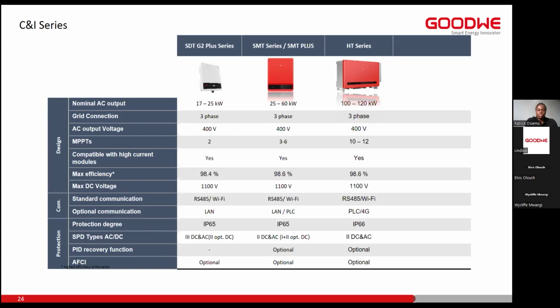And we do have high efficiencies. You see our maximum efficiency is 98.4%. And we support big string connections. You see our MPPT is able to handle up to 1100 volts DC. Different or flexible ways of communication: RS-485 for long distance, Wi-Fi for short distance, LAN, and PLC for specific inverter series.